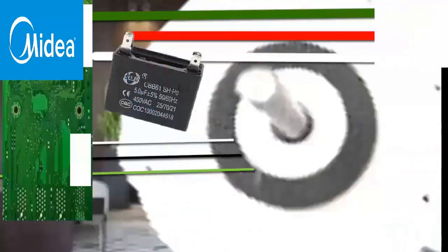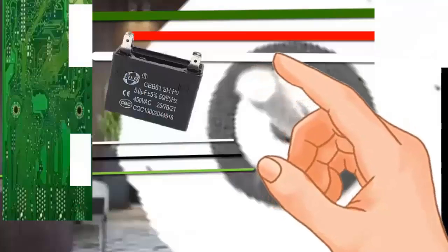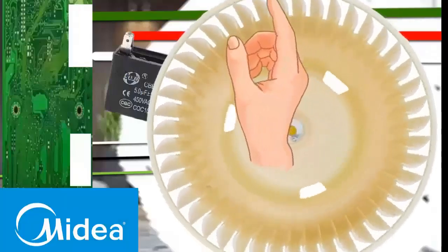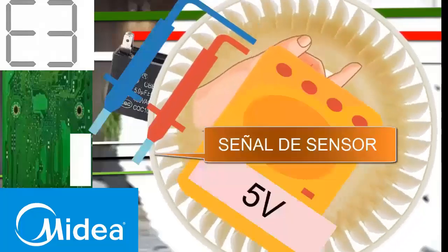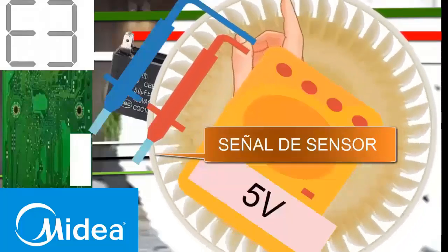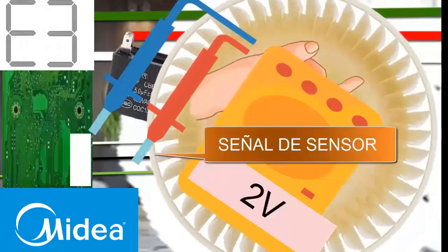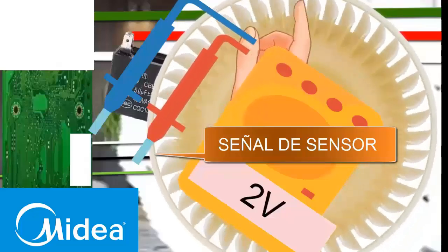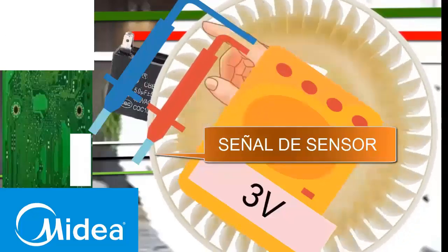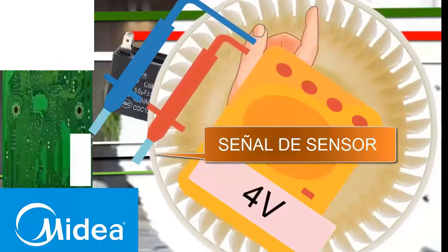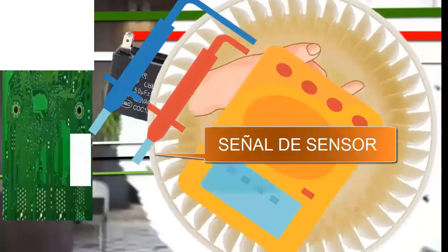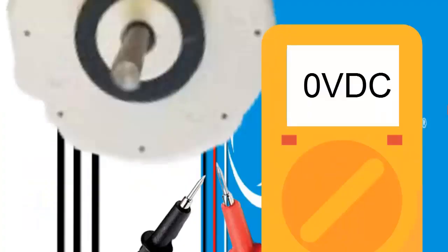10. If there is proper power, 5 or 12 V, to the fan sensor, manually spin the fan and measure the voltage on the signal wire. To do this, place the red probe on the signal wire, and the black probe on the ground. The voltage should change as the fan is manually spun. If there are no changes in the measured voltage, the problem lies in the sensor.